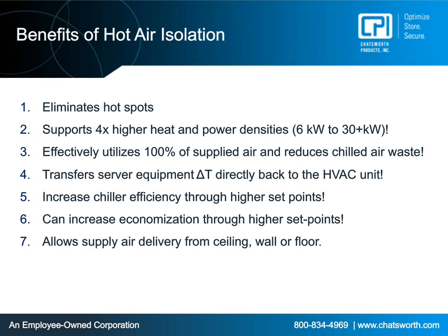Secondly, you can support higher and higher heat loads. We have a couple of cabinets running right now currently in the U.S. at actually 42 kilowatts. So my slide says 6 kW up to 30 kW, but we actually have a couple that are past 30 kW and are up to 42.